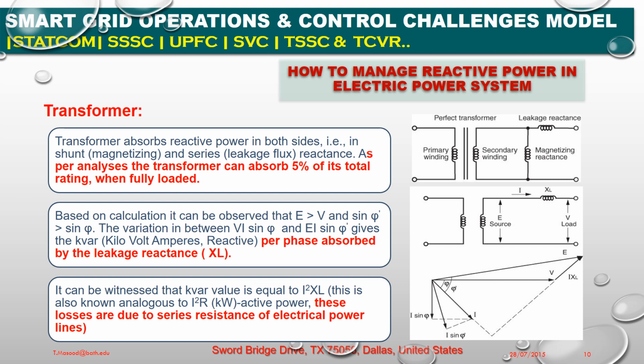Reactive power management in the transformer. If we look here, the transformer absorbs reactive power in both places: in the shunt magnetizing reactance and in the leakage reactance, which is the series reactance. As per analysis, the transformer can absorb 5% of its total rating when fully loaded. Number two, based on calculation, it can be observed that E is greater than V. This is my source voltage E and this is my load side voltage V.